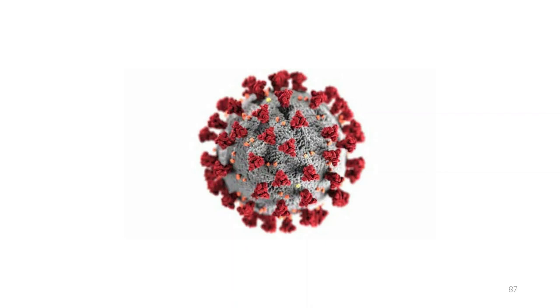You might be thinking, this information is useful, but what do I do about COVID-19? ASHRAE has published guidelines for schools and offices, and at the time of this recording, those guidelines generally encourage an increase in ventilation rate coupled with MERV 13 or higher filtration. They also recommend isolation rooms for sick individuals awaiting transport and room air cleaners where possible.